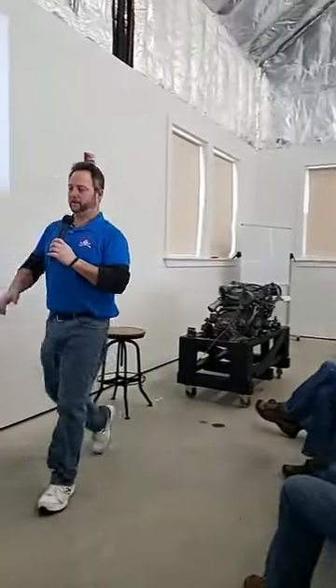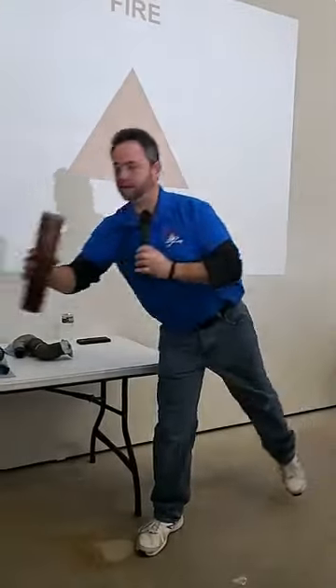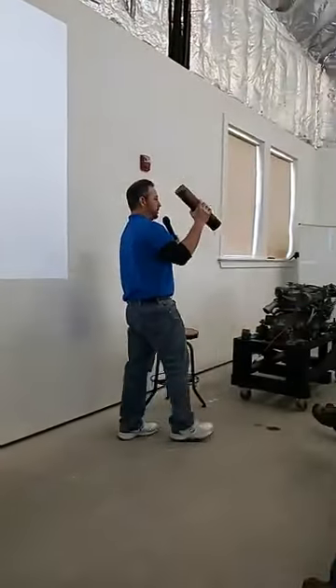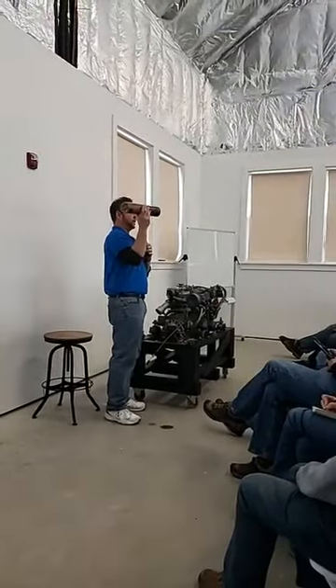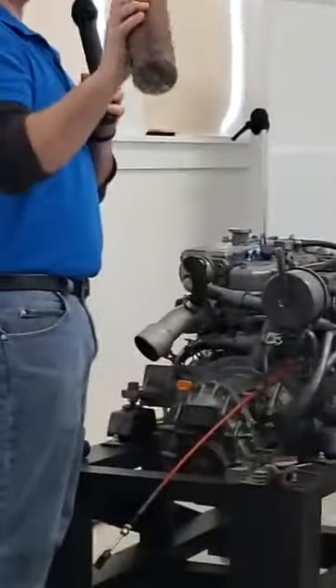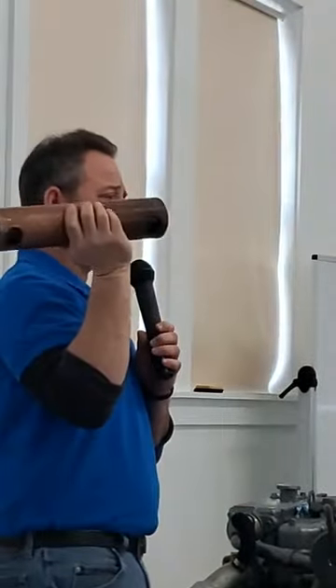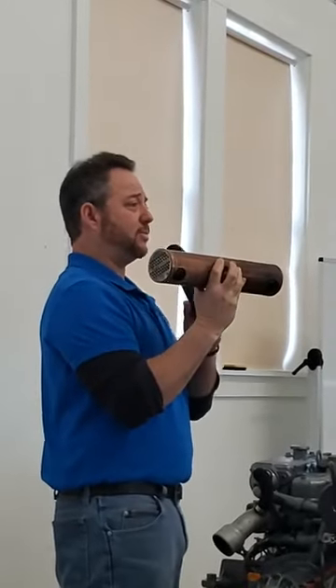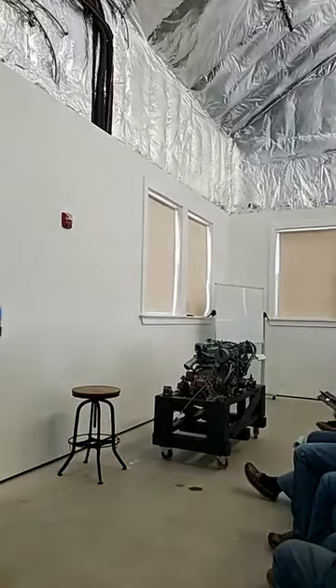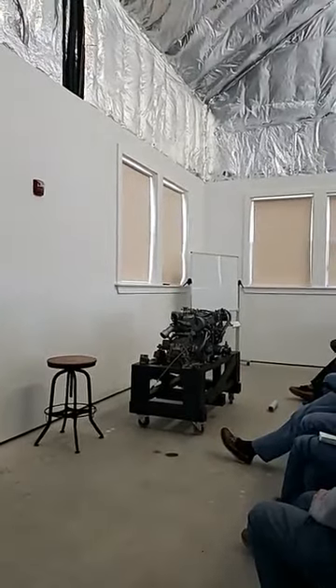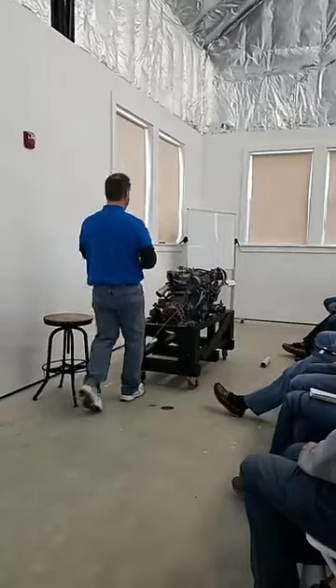So if it's made out of copper-nickel and copper like this one - this one hasn't been cleaned - you can use muriatic acid on it. There are a couple companies doing sonic cleaning now, but a lot of heat exchangers, like from Yamaha, instead of a copper sleeve have an aluminum sleeve. You can't use muriatic acid on aluminum - well, you can, but it'll only last about 30 seconds before it turns to Swiss cheese.